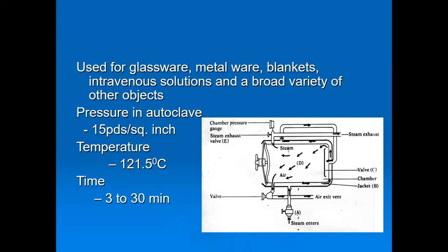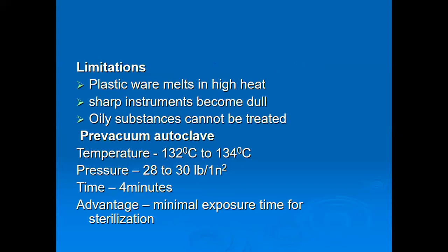Autoclave, you know the pressure cooker mechanism. You know very well 121 degrees at 15 lbs pressure for 15 minutes. You increase the temperature, you decrease the time.